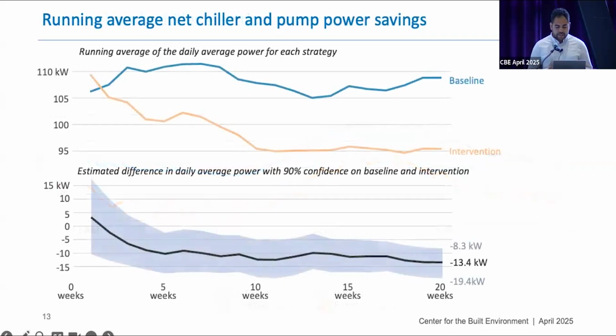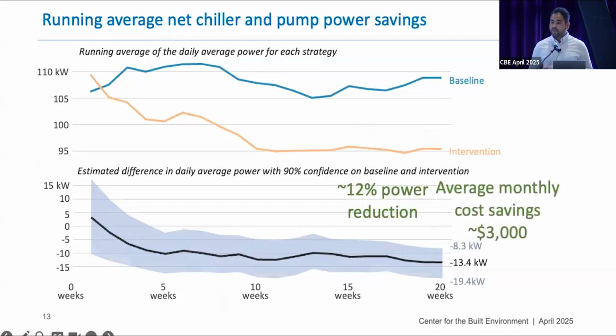So we are still collecting data and constantly updating our running average. And at the moment, we see a total power reduction of about 13.5 kilowatts, which includes the pumps of the chilled water plant. Which represents 12% power reductions, which we're saving about $3,000 per month with just this simple intervention.